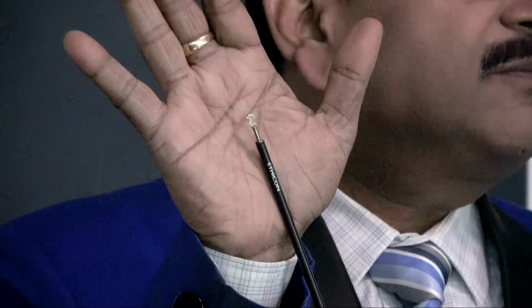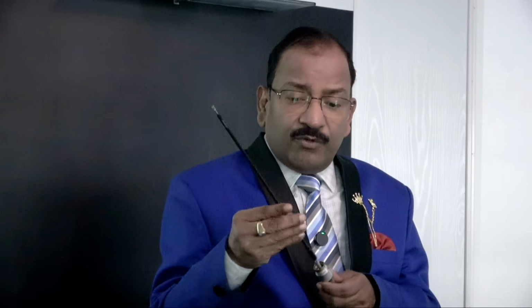So there is a piezoelectric crystal inside, and once current comes here it vibrates, and anything you attach to the piezoelectric crystal vibrates. Your ultrasound machine also has a transducer with a piezoelectric crystal. But we use only the sound part of that crystal to do ultrasound, whereas here we are using the mechanical part of that piezoelectric crystal. And in this screw you can attach anything. You can attach the hook. This is the harmonic hook and I have attached it. You can see it is a simple hook, and you can use it for cholecystectomy, colpotomy, partial nephrectomy. This is the harmonic hook, very useful. Then you have a harmonic ball, harmonic shear, harmonic ace, harmonic wave.